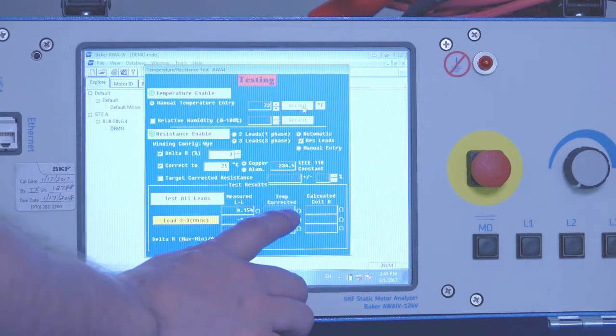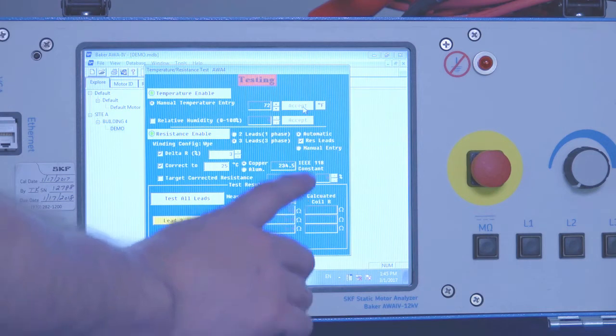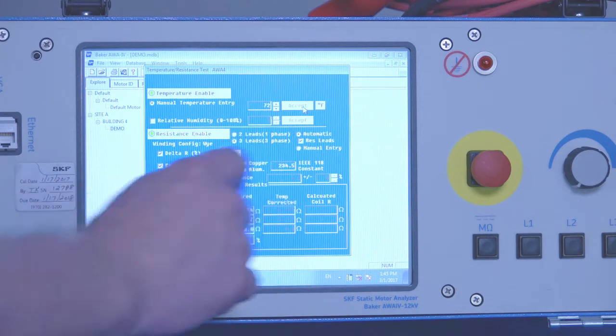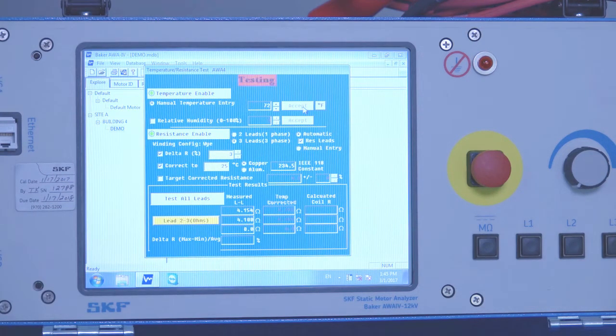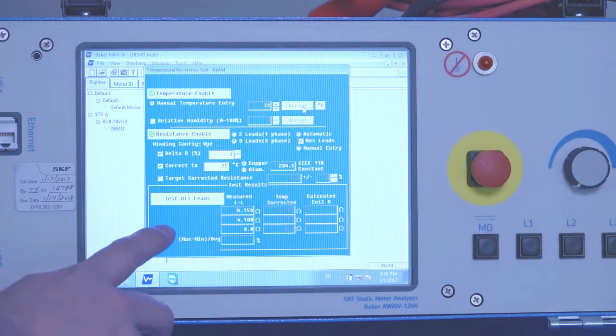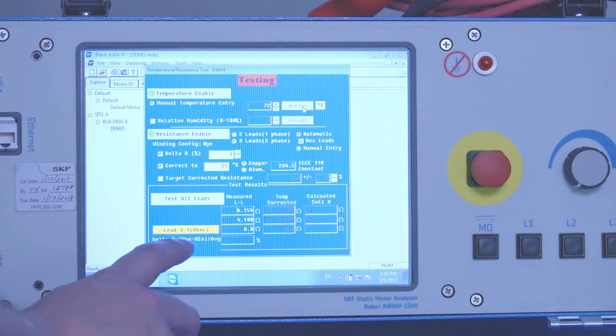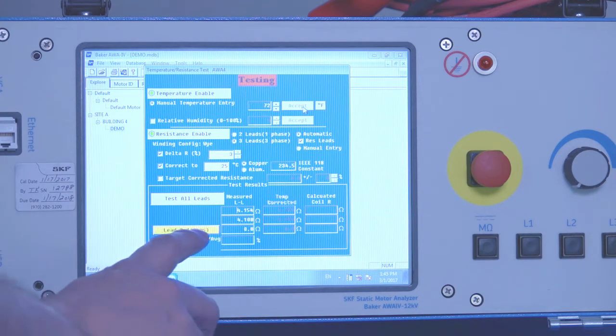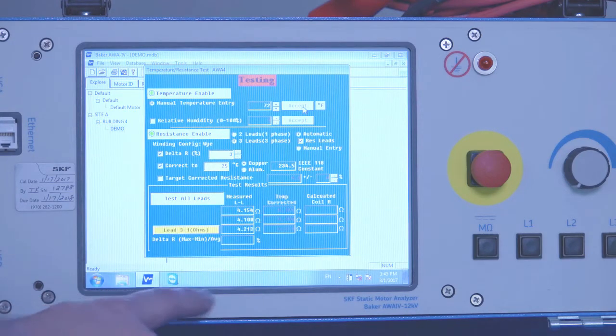The temperature corrected resistance is populated based on the temperature that we entered earlier. Now it's doing two to three. And now it's moving on to lead three to one. So the three independent measurements that are taken.